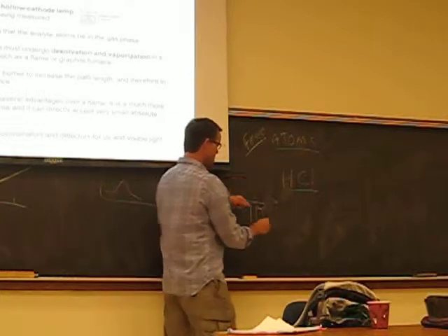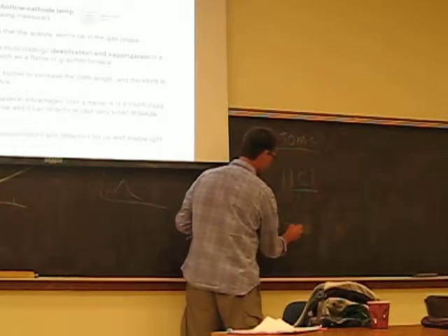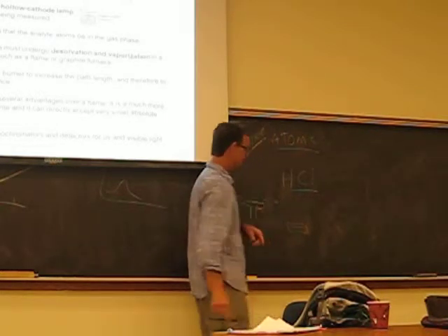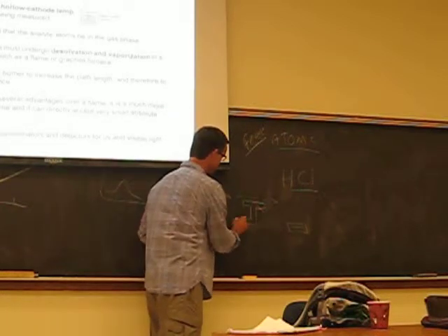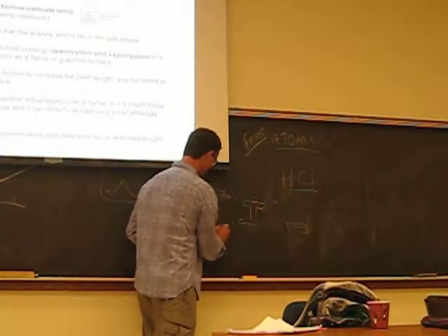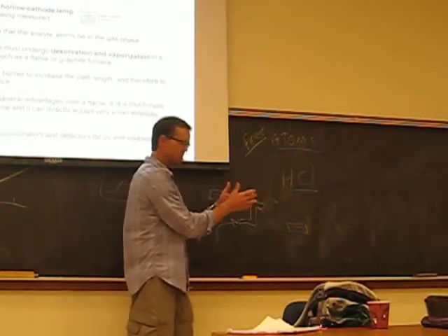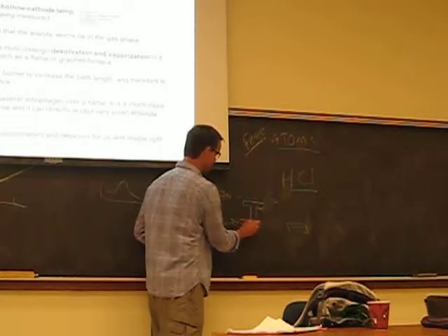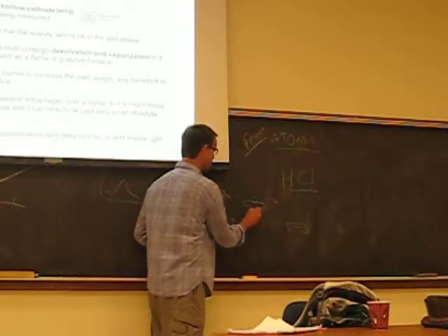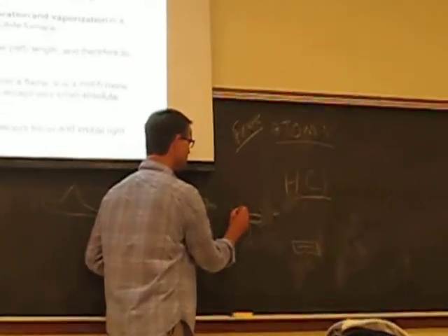If I were to look down from the top of the burner, there's a slot right in that burner end that's about a millimeter or half a millimeter wide. And there's a bunch of plumbing down here, and our sample gets introduced into the burner with gas sucking it in with the Venturi effect, and it gets aerosolized in this nebulizing chamber that we'll talk about, and it gets put into a very, very fine droplet mist up into the flame here.